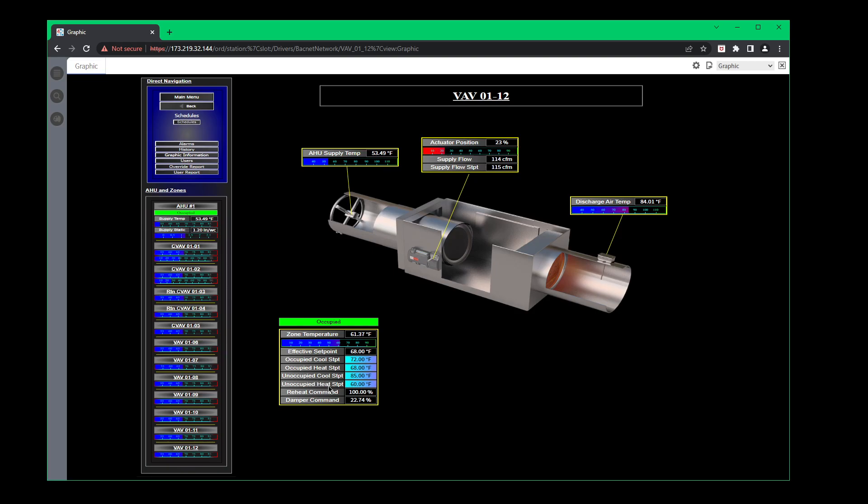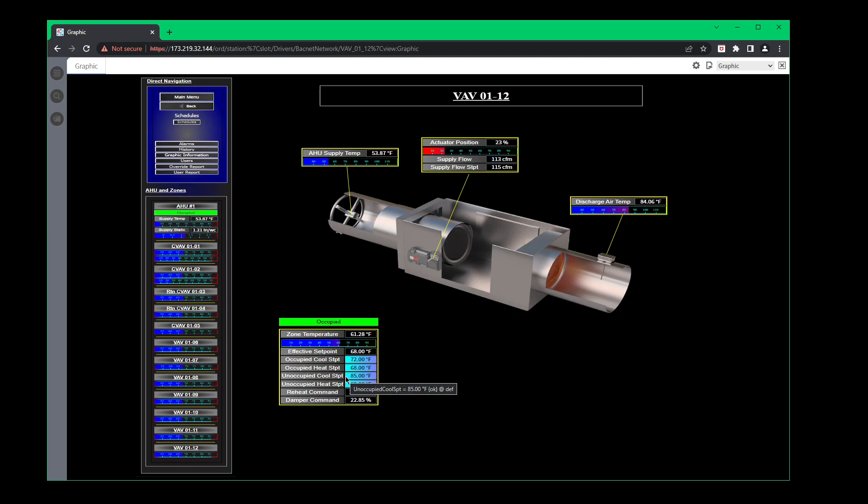Unoccupied cooling heat set points are set up for when the building's unoccupied in the evenings. That way, if the building gets any colder than the heating set points, it'll bring the air handler on to move some air flow so it can help warm up the building so you don't get it too cold. Same thing with the cooling set point for unoccupied. If the building starts getting above 85, it'll bring the air handler on and then temper your building back down. And then after it's been running for about minimum of 30 minutes to an hour, so we don't get any short cycling, the air handler will shut back off and it'll come back on based on your schedule.